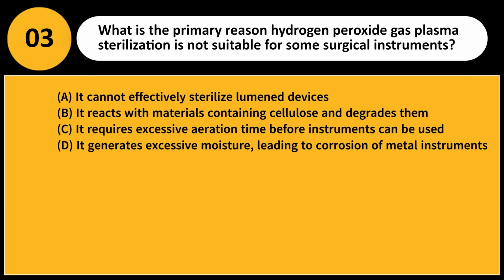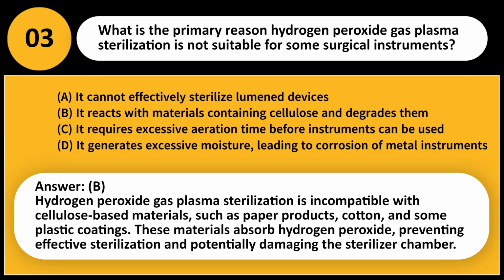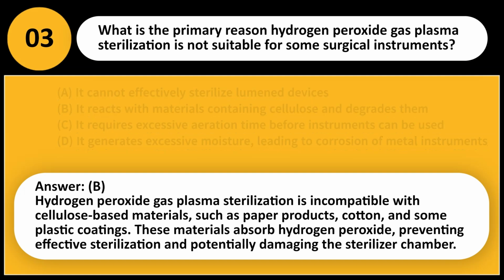Answer, B. Hydrogen peroxide gas plasma sterilization is incompatible with cellulose-based materials, such as paper products, cotton, and some plastic coatings. These materials absorb hydrogen peroxide, preventing effective sterilization and potentially damaging the sterilizer chamber.